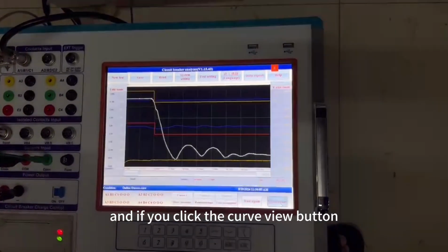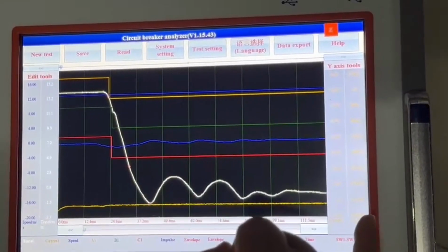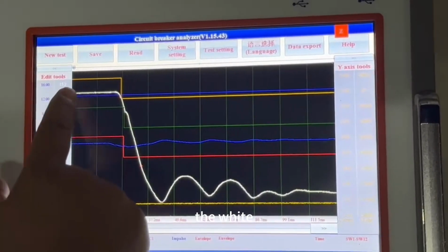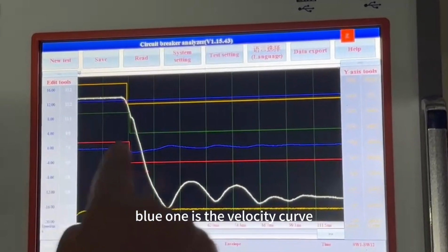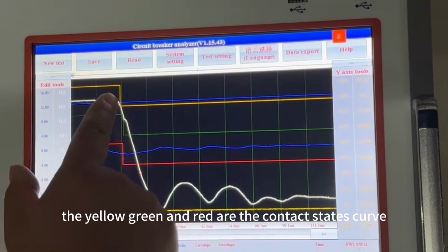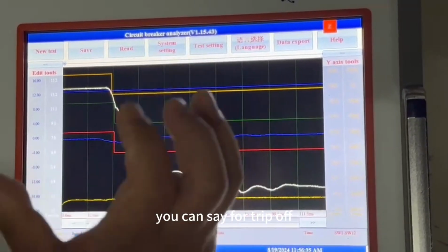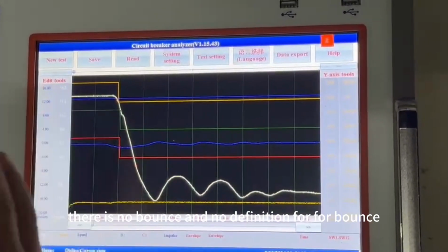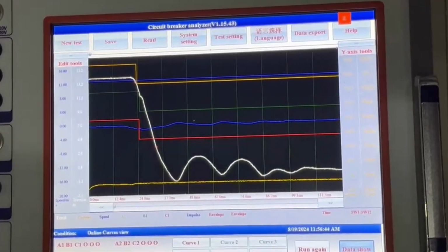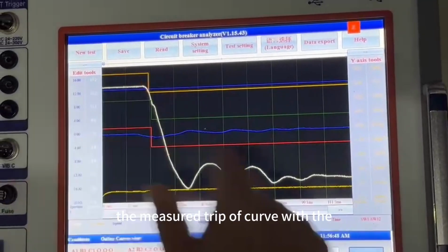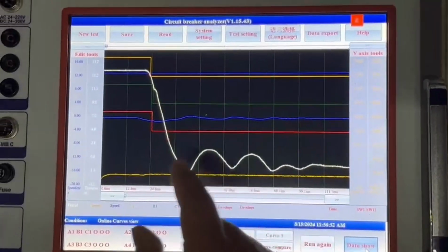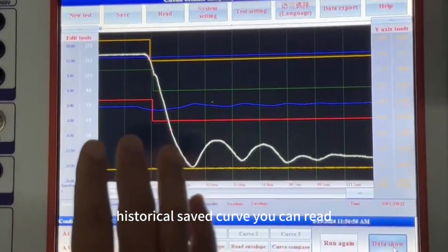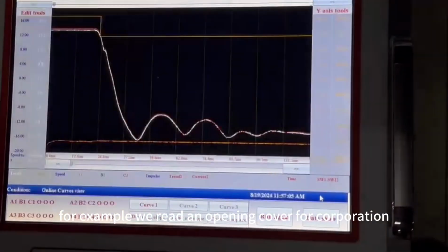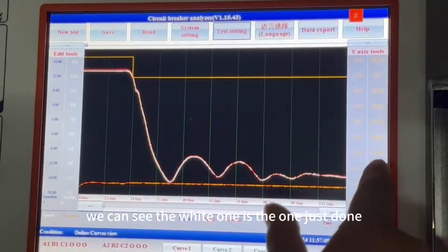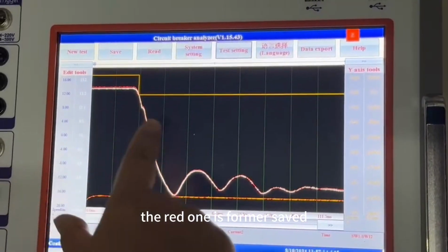And if you click the curve view, current of the trip off coil, the white curve is the travel curve, the blue one is the velocity curve. The yellow, green, and red are the contact state. You can see for the trip off test or opening test, there is no bounce and no definition for bounce. The same, if you want to compare the measured trip off curve with the standard requirements or with the historical saved curve, you can read the curve for comparison. For example, we read an opening curve for comparison. We can see the white one is the one just done. The red one is the saved trip off curve.